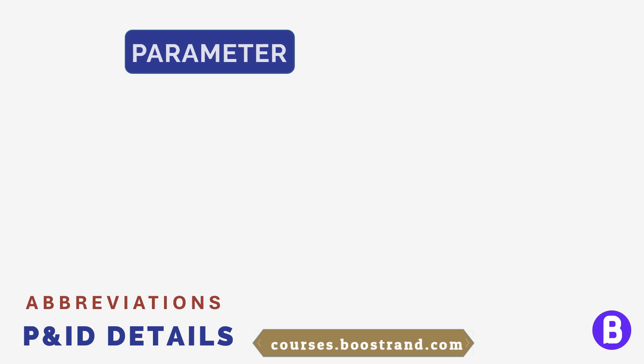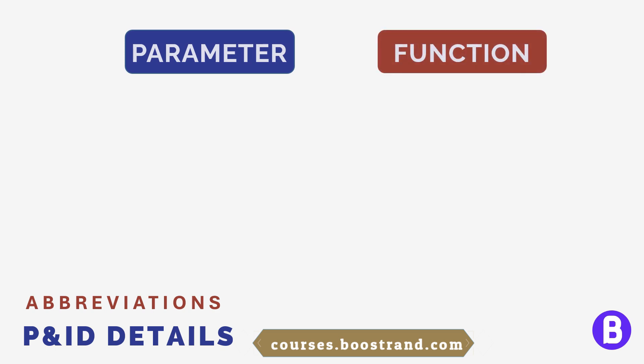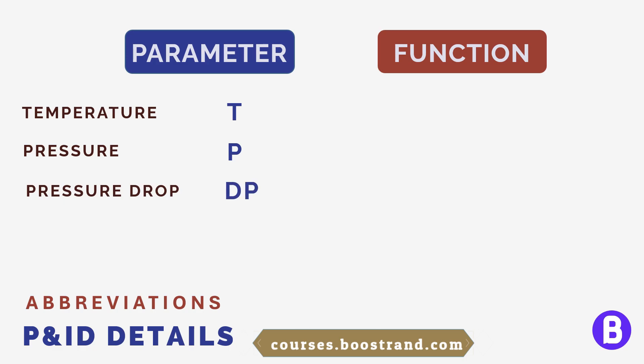Here I would like to show how the identification of these components is shown in a P&ID. We can see that any instrument, controller, or final element has an abbreviation containing two main things: the first is the parameter it is serving, and the second is its function. For example, for a temperature-related device, the parameter letter shall be T. For pressure it shall be P, and for pressure difference it would be DP — sometimes called PD depending on the legend the designer is following.